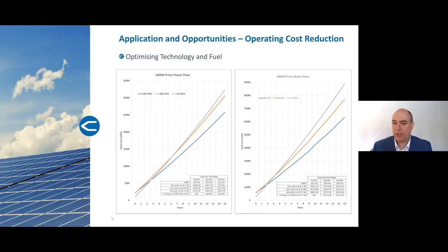A white paper presented by Inglet and Stubbs in 2019 looked at the impact of running high-speed generators versus medium-speed units utilizing diesel fuel. Heavy or high-speed units typically run at between 1,200 and 1,500 revolutions per minute, while medium-speed generators run between 700 and 1,000 revolutions per minute.